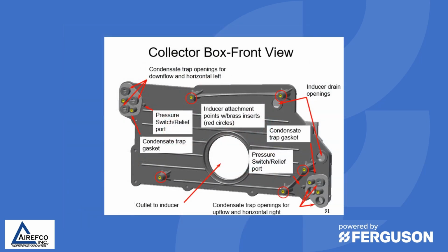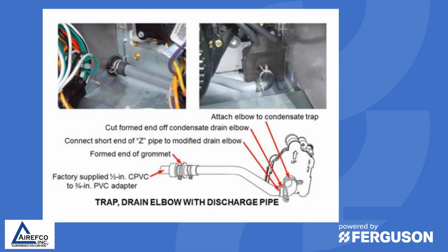This inducer housing is mounted onto the collector box or the front plate of the furnace, and this front plate is also designed to direct the vent gases into the induced draft motor to exit the furnace, and also to direct the condensate to the condensate trap to be deposited outside the furnace. One of the main misconceptions that technicians have about 90% condensing furnaces is that the furnace is not able to handle the condensate that is coming back into it from the vent.